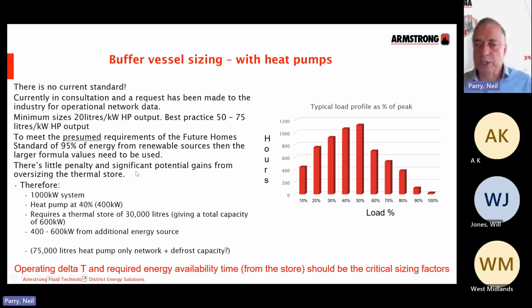So I'm going to just jump to the bottom statement there. Really, for me, heat networks are all about delta T and thermal difference rather than kilowatt output. So the way I tend to look at thermal storage is I look at the operating delta T, and how long do you want the energy to be available from that thermal store? Those two critical factors, I think, are much better for calculating your thermal store size using those two values.